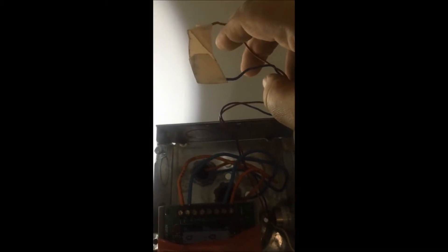They're not wired together. It does leave the trouble in. I was told if you want to clear the trouble, you can put a jumper between the red and blue. I didn't do that because my high-low and my water flow came in above it on the preactions. But in case you're ever out here at Westwood, it's kind of how you do it.